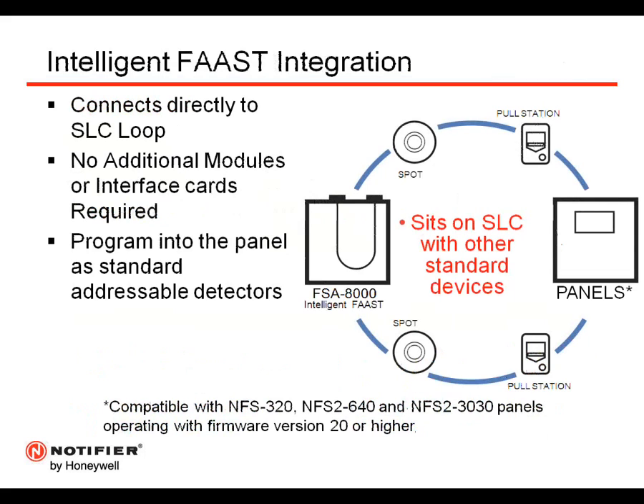We can compare that with an intelligent FAAST integration. Connects directly to the SLC loop. No additional modules or interface cards required, again, to be purchased, installed, wired, configured, potentially troubleshot. And it programs into the panel as just a standard addressable spot detector. So it just sits on the SLC loop with the standard devices.